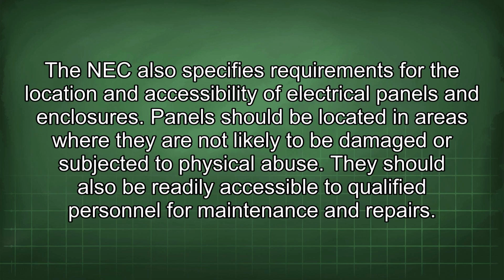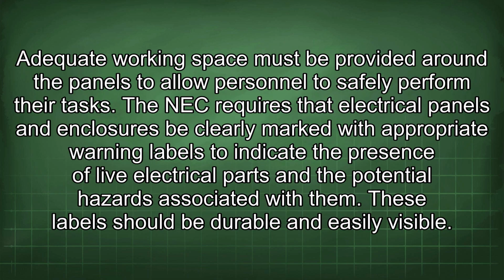The NEC also specifies requirements for the location and accessibility of electrical panels and enclosures. Panels should be located in areas where they are not likely to be damaged or subjected to physical abuse. They should also be readily accessible to qualified personnel for maintenance and repairs. Adequate working space must be provided around the panels to allow personnel to safely perform their tasks.